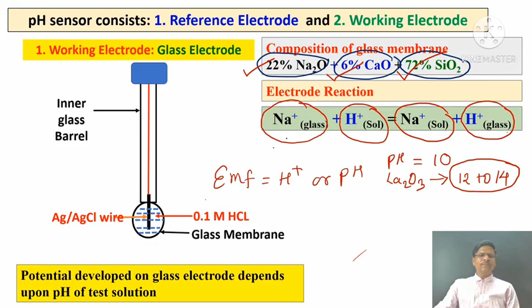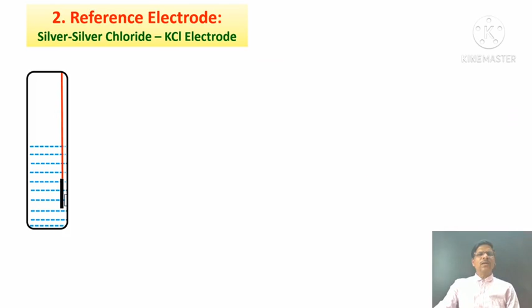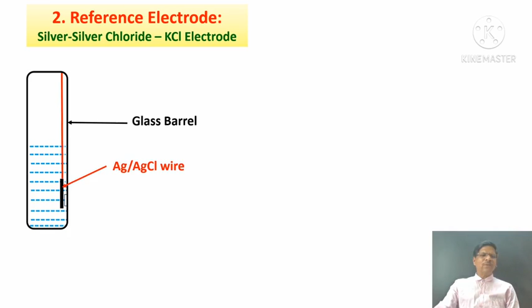So this is the working electrode. Now we have the reference electrode. The reference electrode is a silver chloride electrode consisting of KCl. We have a glass barrel. Inside the glass barrel, a silver chloride wire is fixed, and saturated KCl solution is filled into the glass barrel. This becomes the reference electrode. A porous plug is fitted so that an electrical connection can be established between the test solution and the reference electrode.